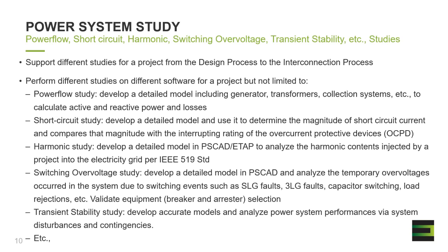power factor criteria by ISOs, performing short circuit study to ensure that the balance of plant cables and the switchgears and equipment will not be damaged in case a fault occurs in the BOP.